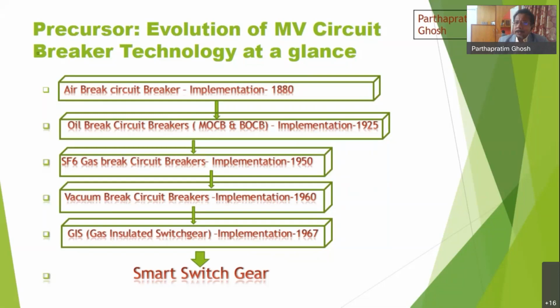In case of the air circuit breaker, the major insulation is air, and the arc interruption happens also in the air. There is a different version of air circuit breaker which is still in use, particularly in the EHV segment, that is air blast circuit breakers. Oil circuit breakers nowadays are almost obsolete. It was implemented in around 1925.